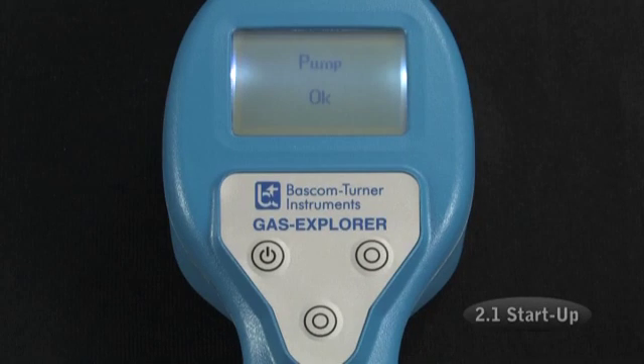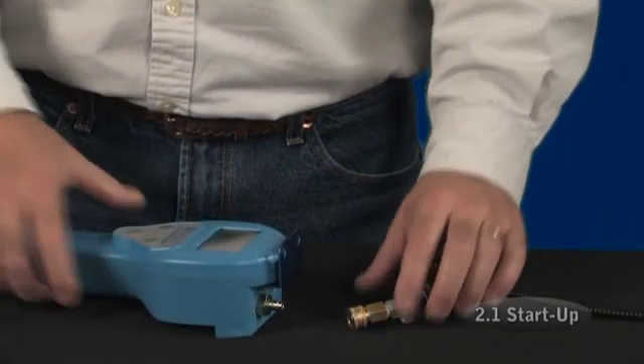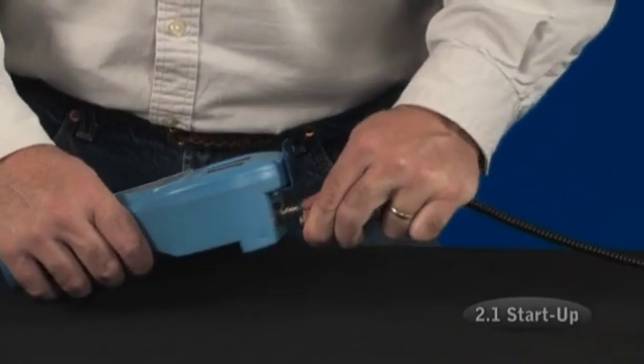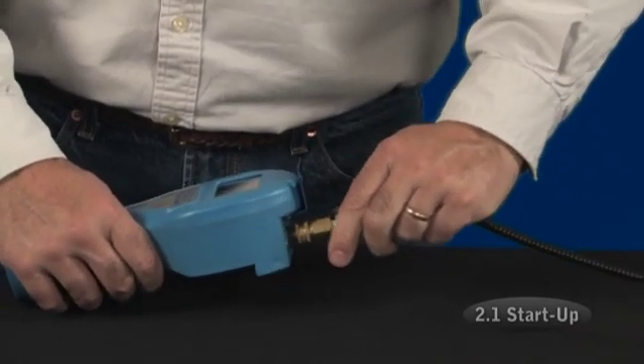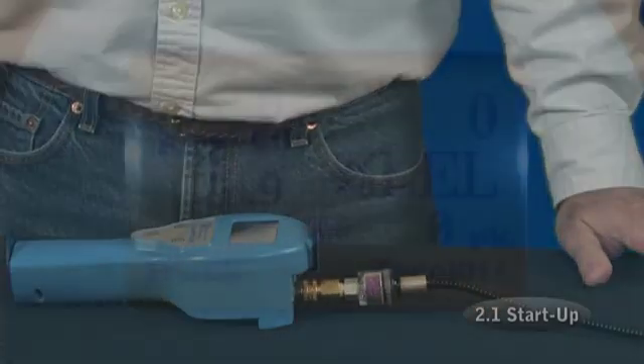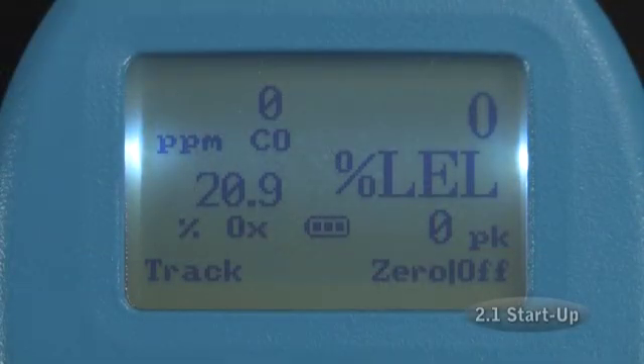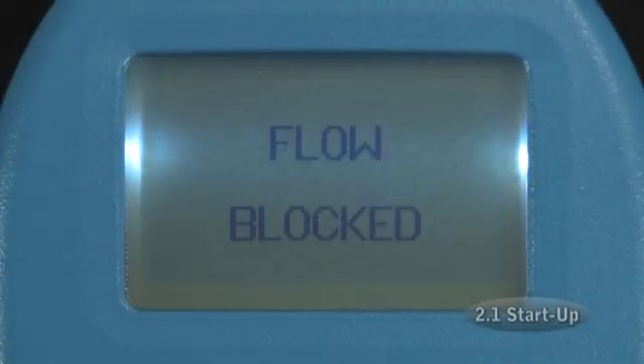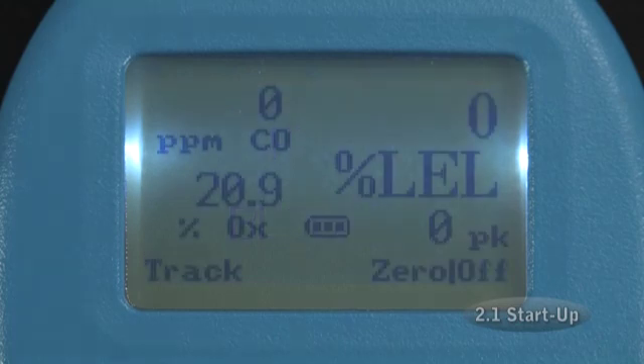If it does not detect a block, it will say, "Pump OK," and you know that your sampling system was not tight. Reassemble the filter and the components of the selected probe, making sure that all connections are tight. Once the detector is in the monitor mode, check the probe by blocking the tip to display "Flow blocked" on the Explorer. If at any time you suspect a leak in the sampling probe, check the probe in this fashion.